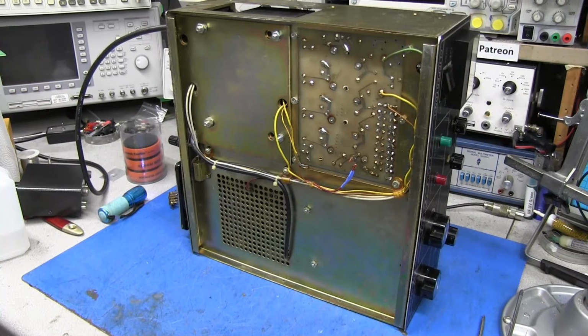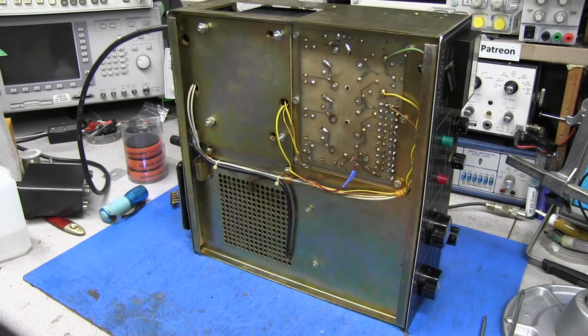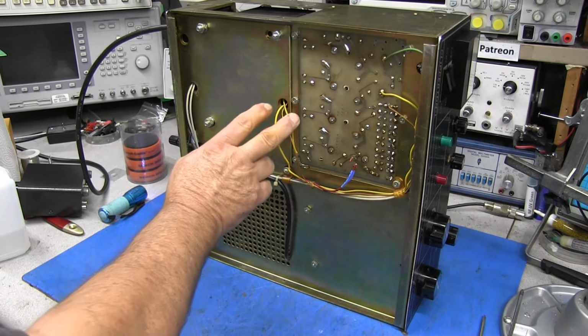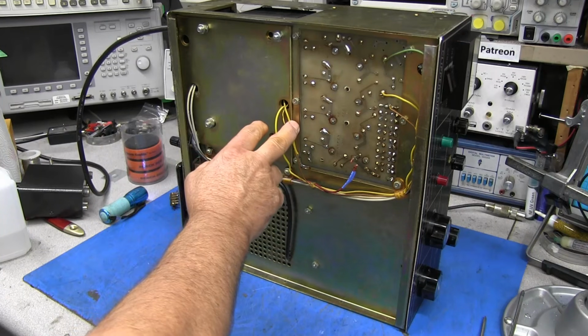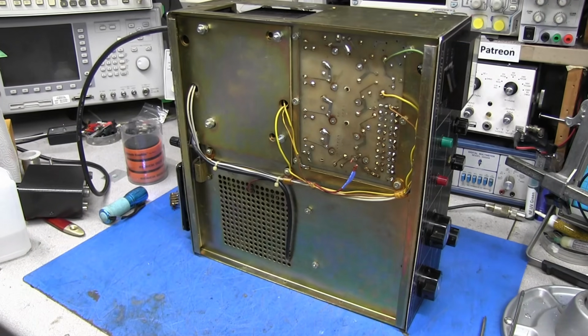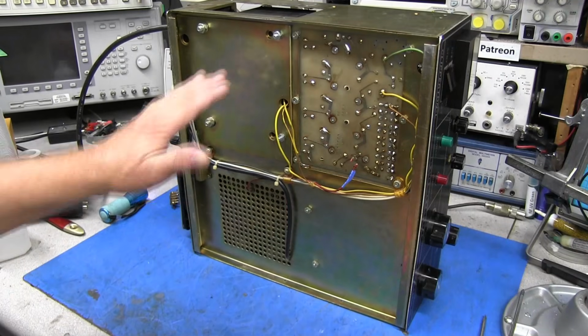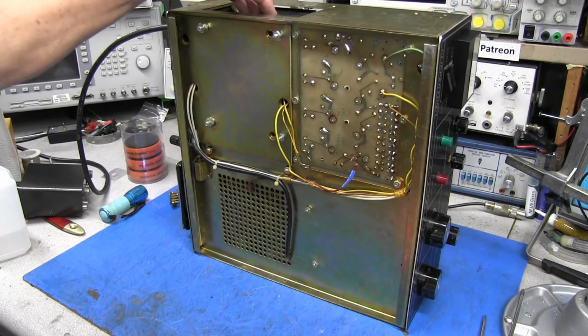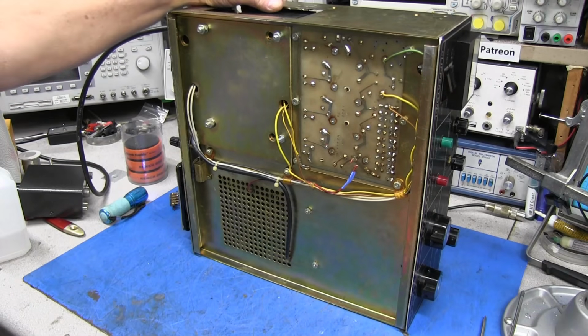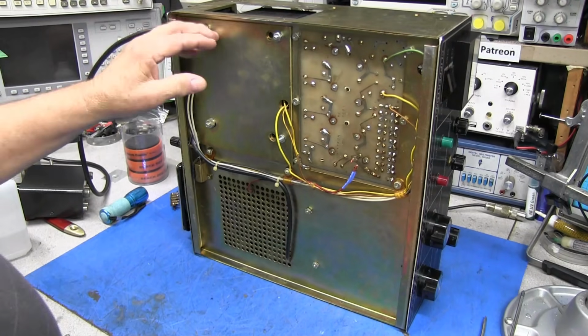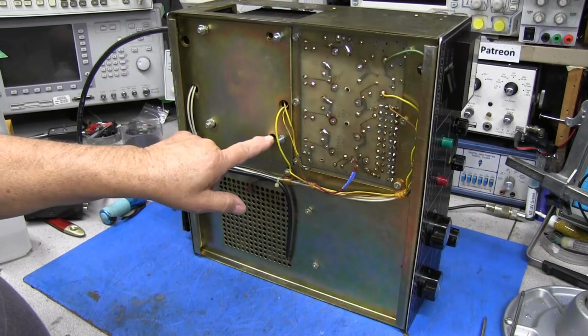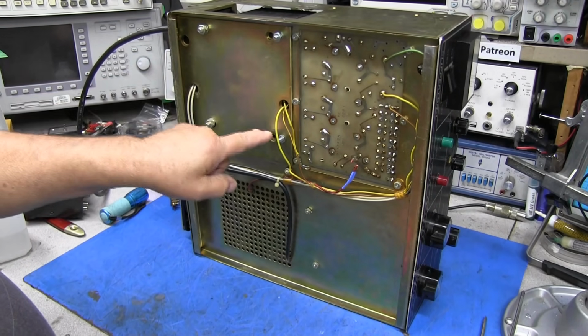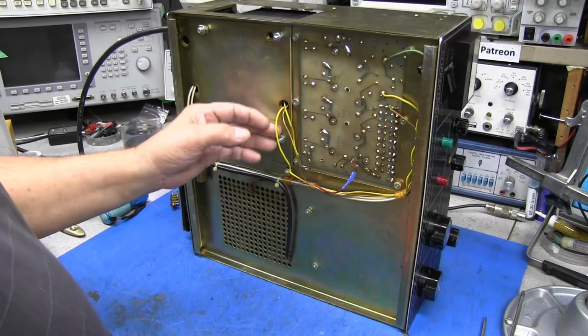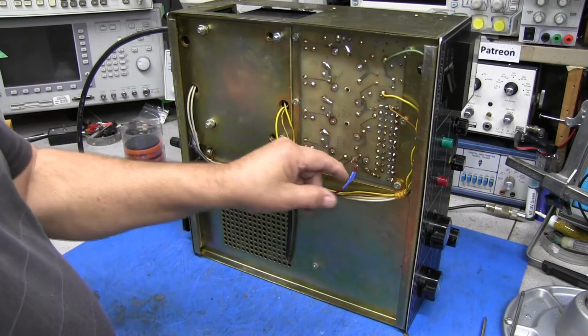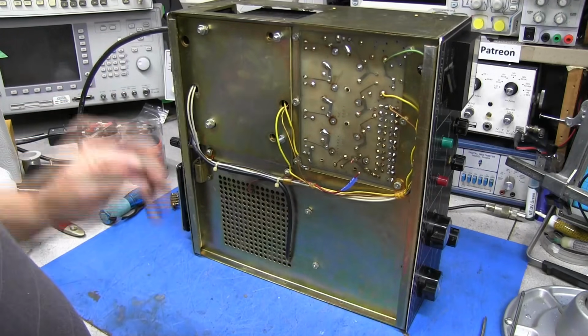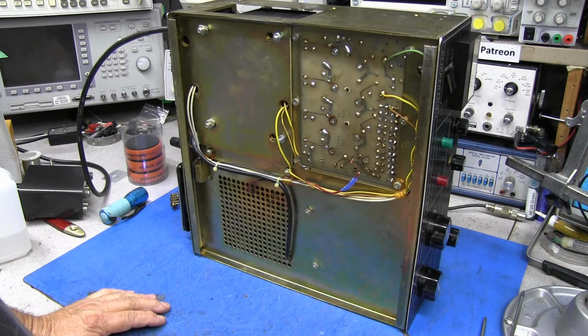So normally there would be a large red or yellow wire and a large orange or red wire down here, but someone has changed out this transformer, and they went with a bigger transformer than what came in it. You can see there's the original two mounting holes, and these are the two new mounting holes. So the issue with that is that our wire colors does not mate up with what we already had.